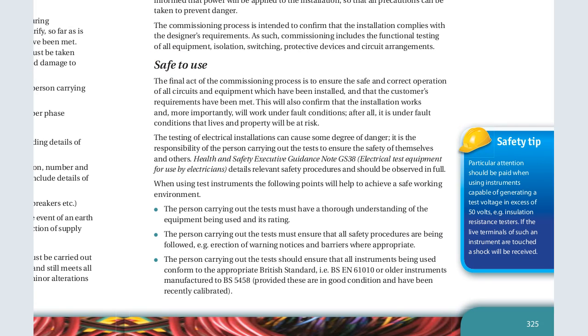When using the test instrument, the following points will help us to achieve a safe working environment. We have to make sure that even when we are working, the environment is safe. That is, the person carrying out the test must have a thorough understanding of the equipment. That is why we go through the training, so that we can understand what is needed or required when doing the inspection. The person carrying out the test must ensure that all safety procedures are being followed, e.g., erection of warning notices and barriers where appropriate. They should also ensure that all the instruments being used conform to the appropriate standards.